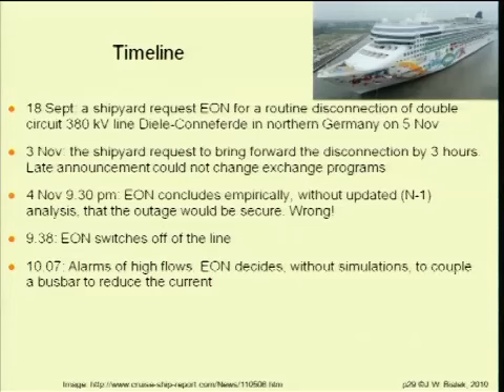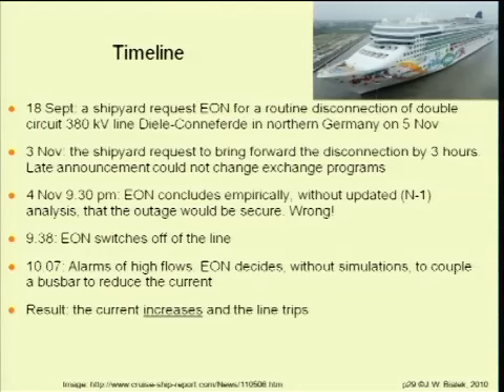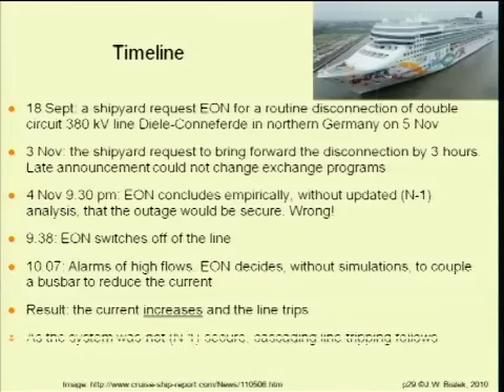So at 9:30, E.ON switches off the line. And half an hour later, there were alarms that the flows in the area are too high, and then E.ON decided again, without doing proper analysis, that they have to decouple a busbar. This is an electrical connection, basically changing slightly the configuration of the network, in the hope that they would reduce the current. It did the opposite. The current increased.